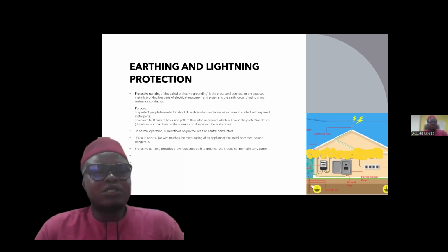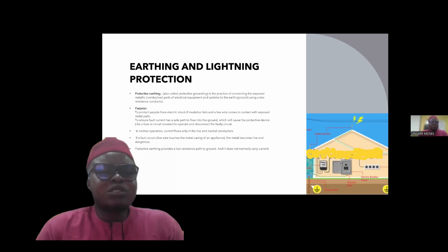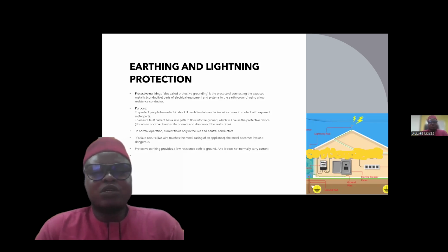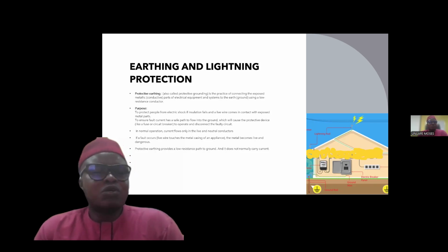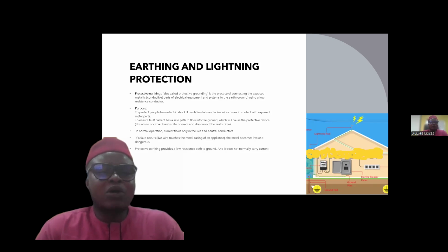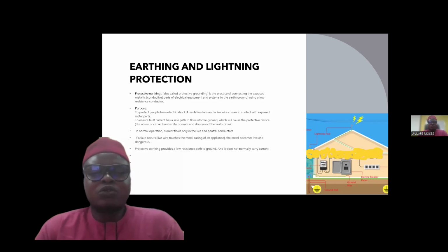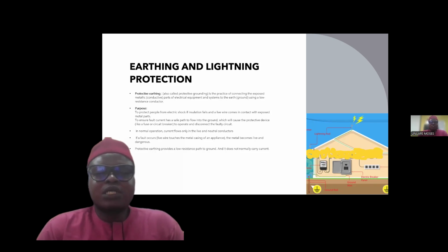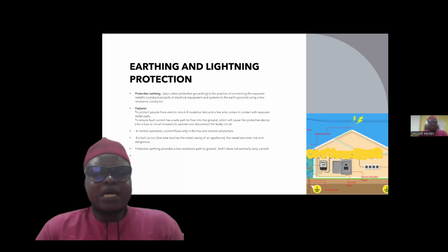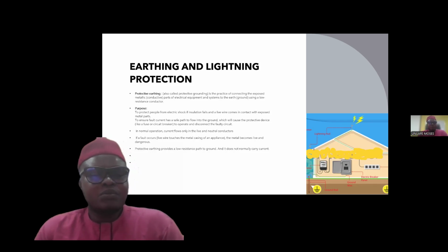Why do we have to do this? The reason why we need to do this is to protect people from electric shock if insulation fails or a live wire comes in contact with the exposed metallic part or a personnel. It also ensures a fault current has a safe path to flow to the ground, which will cause the protective device to operate and disconnect the fault circuit.